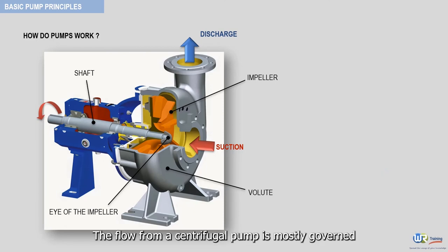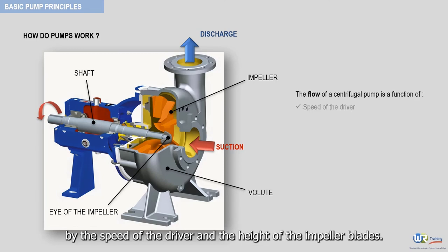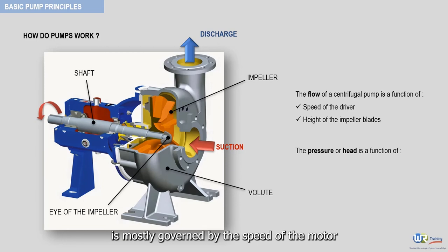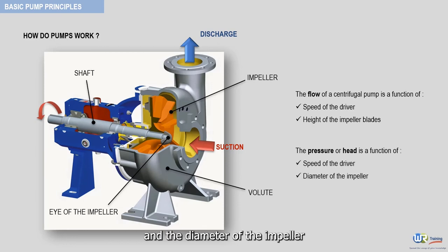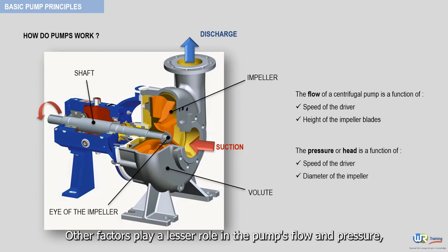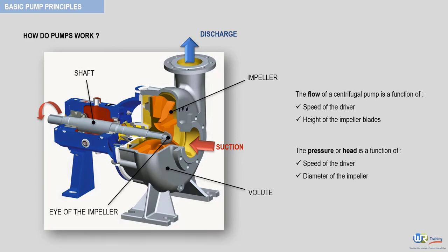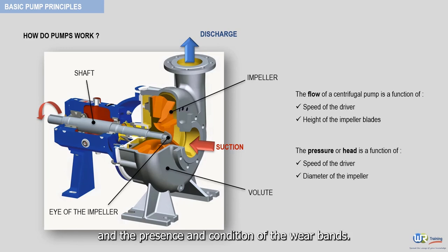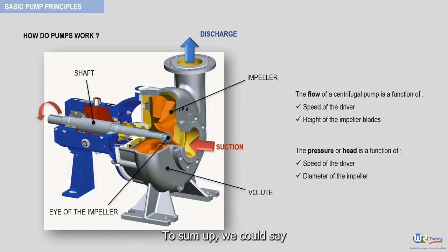The flow from a centrifugal pump is mostly governed by the speed of the driver and the height of the impeller blades. The pressure or head that these types of pumps can generate is mostly governed by the speed of the motor and the diameter of the impeller. Other factors play a lesser role in the pump's flow and pressure, such as the number, pitch, and thickness of the impeller blades, as well as the internal clearances and the presence and condition of the wear bands. These factors will be covered in detail further ahead.